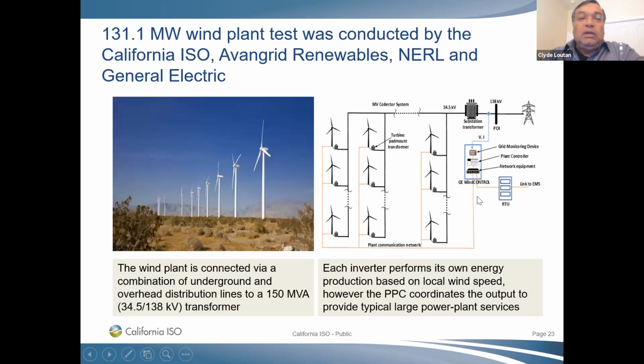Okay, thanks, Clyde. So moving on to the wind test. This was a 131 megawatt wind plant. I forgot to mention that the first test we did was between the California ISO, First Solar and the National Renewable Energy Laboratory. This test was conducted by the ISO, Avangrid Renewables, who own this wind facility, NREL and General Electric. When we did this test, it was a similar configuration: individual inverters controlling turbines, and a controller that sits right here. As I had mentioned with the solar plant, this smart plant controller controls the individual inverters to make the plant respond to signals from a balancing authority like the ISO.